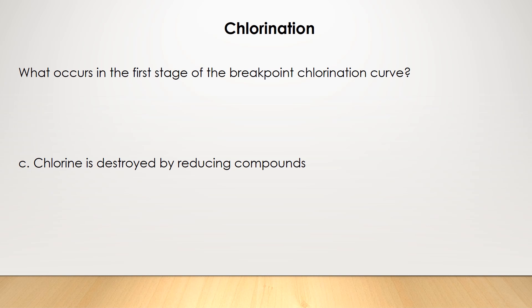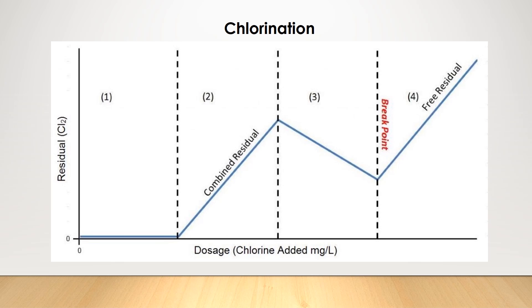Let's go over the breakpoint chlorination curve so you know why this is the correct answer. The curve tells you what's happening to the chlorine that you're injecting into the water. Starting on the left side of the graph at Stage 1, the chlorine is being destroyed by what's called reducing compounds — things like iron and manganese that are naturally present in the water. Because chlorine is reacting with these reducing compounds, there are no chlorine residuals formed. The blue line at the bottom shows the chlorine residual concentration is close to zero. This answers the previous question, but I'll finish explaining the remaining parts of the chart.